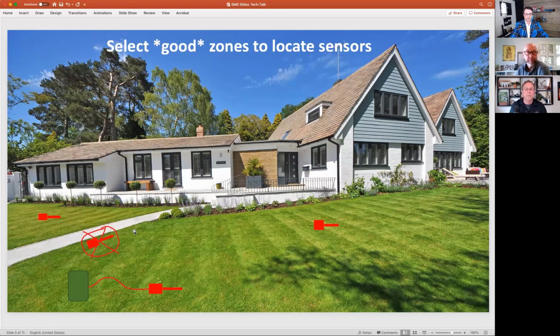Yeah. And today we don't have enough time to talk about all the ins and outs on how to install it, how to hook it up, how to wire it, and all of that. We'll have to touch on that later. But I did want to just draw a valve box and remind you that on a retrofit situation, the sensor gets wired to the closest zone valve, and that removes the need to run a home run wire all the way back to the garage.